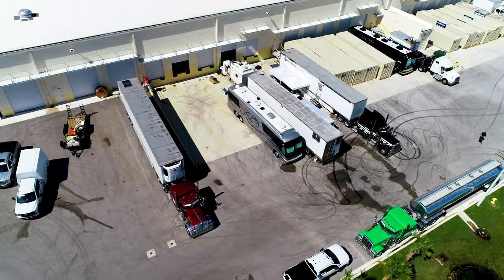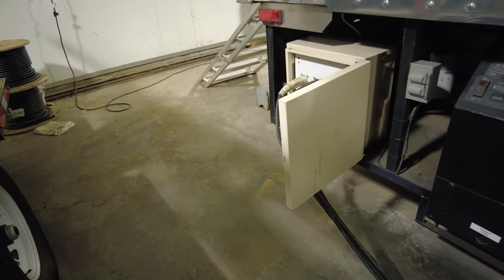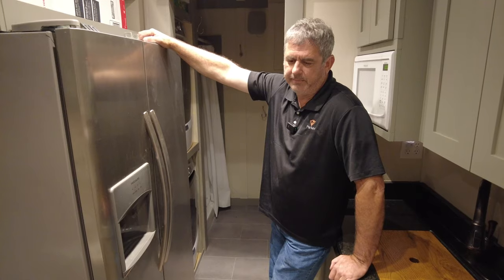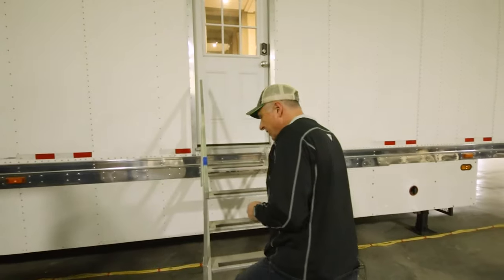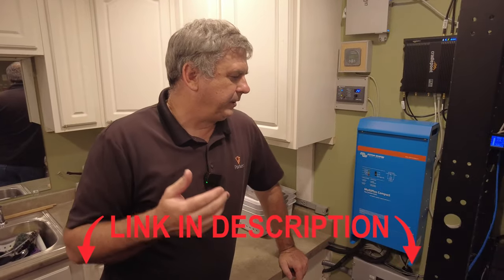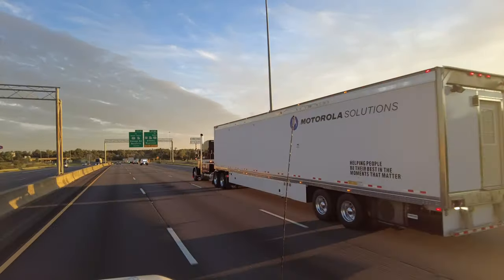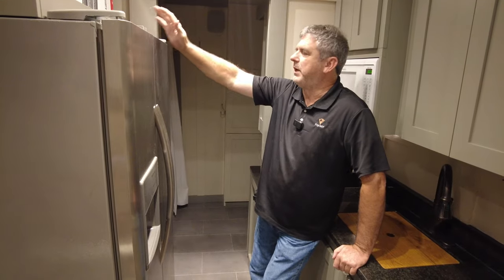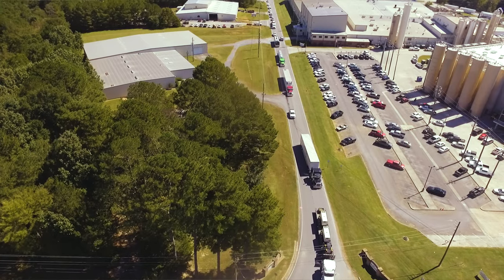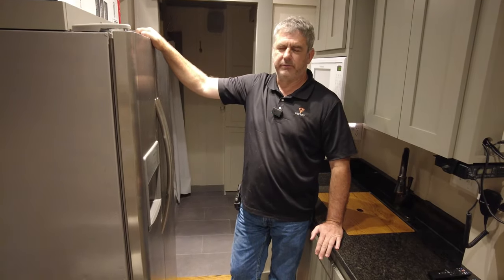When we deploy we have three trailers that end up having our food stores in them. One of them is in Sleeping Trailer 2 — we have a full-size refrigerator with a freezer. This trailer has a generator that is about 12,500 watts — it's a little diesel Onan under the back of this 53-foot refrigerator trailer we've converted into a sleeping trailer and an office trailer. We have a 2,000-watt inverter, and all that inverter does is run this refrigerator. There are two Battle Born batteries. The inverter system and refrigerator draw about 400 watts at 50% duty cycle, and with the 200 amp-hour batteries we get about 48 hours of runtime. So if we were to lose the generator the minute we left, we wouldn't lose our freezer, our refrigerator, or all the food in this trailer because we have 48 hours of backup.